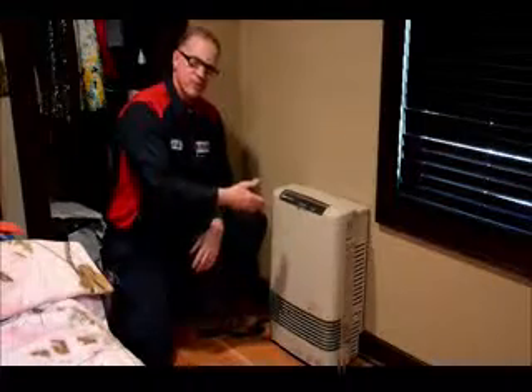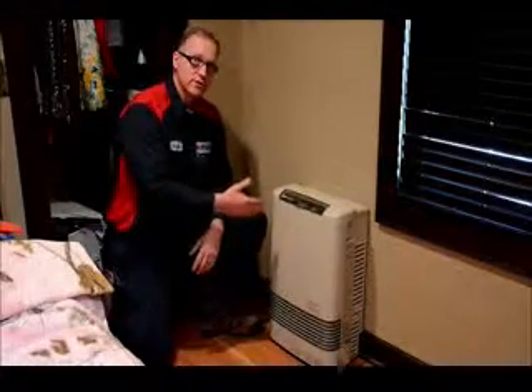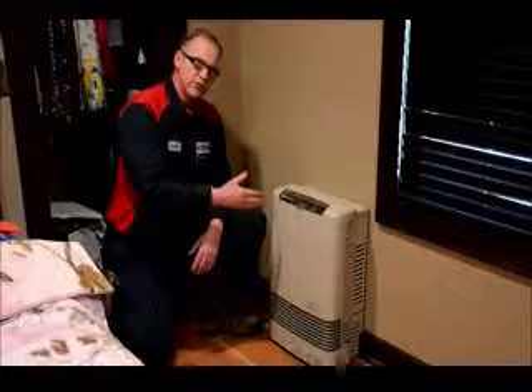The advantages of the Rinnai direct vent furnace are if you have a cold room, a cold basement, you're adding on to your home and you don't want to tie into the existing ductwork of your home and damage the performance of the existing ductwork, we can add one of these furnaces in to heat that space. The advantages of the Rinnai direct vent furnace are the ease of install.